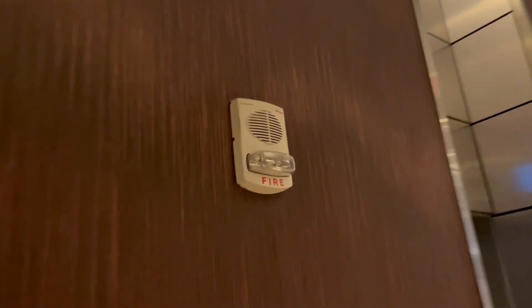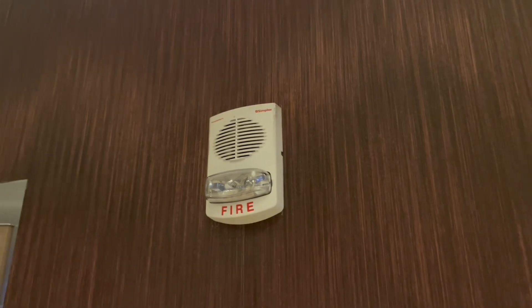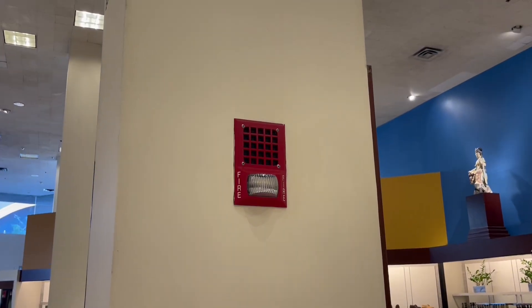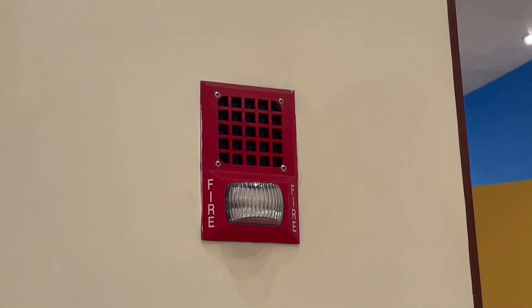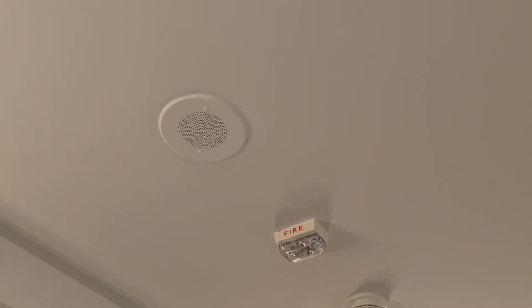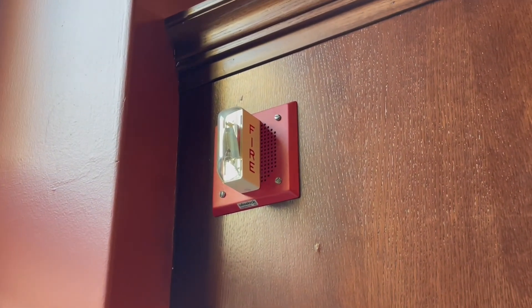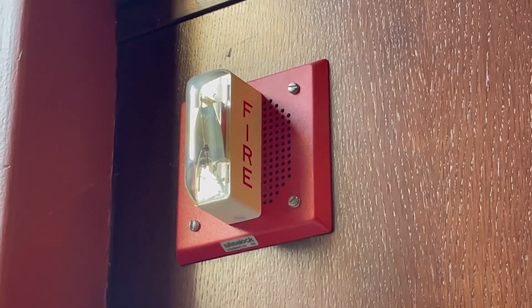This messaging is just one element of voice evacuation systems that has made them more prevalent in recent years. Voice evacuation systems also provide a way for fire departments or other first responders to talk directly to building occupants and provide live information through the fire alarm system. This allows different parts of a building to receive different instructions in an emergency, which ultimately improves the effectiveness of the fire alarm system. Here's an example of this: when the fire department arrives on scene, they give live updates to the fire alarm speakers.